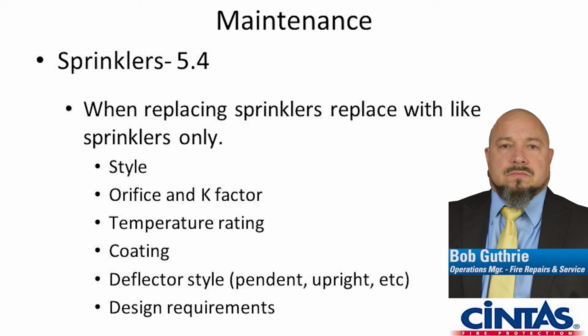Sprinkler heads, when they're engineered, are also designed with what we call an end head pressure. And that means the minimum amount of PSI that has to be delivered at that sprinkler head for it to operate and give you the amount of water and the spray pattern that has been listed for that sprinkler. So all these things have to be taken into account when you're replacing a sprinkler.